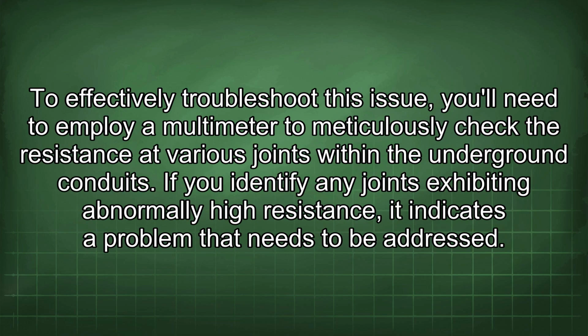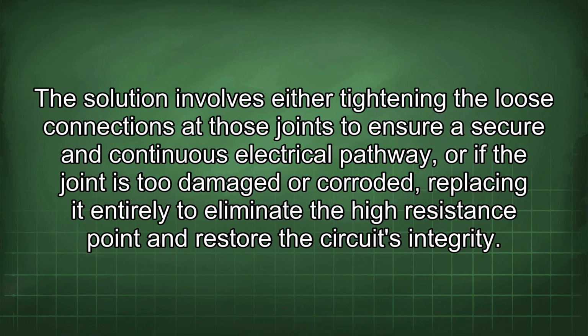To effectively troubleshoot this issue, you'll need to employ a multimeter to meticulously check the resistance of various joints within the underground conduits. If you identify any joints exhibiting abnormally high resistance, it indicates a problem that needs to be addressed. The solution involves either tightening the loose connections at those joints to ensure a secure and continuous electrical pathway, or if the joint is too damaged or corroded, replacing it entirely to eliminate the high resistance point and restore the circuit's integrity.